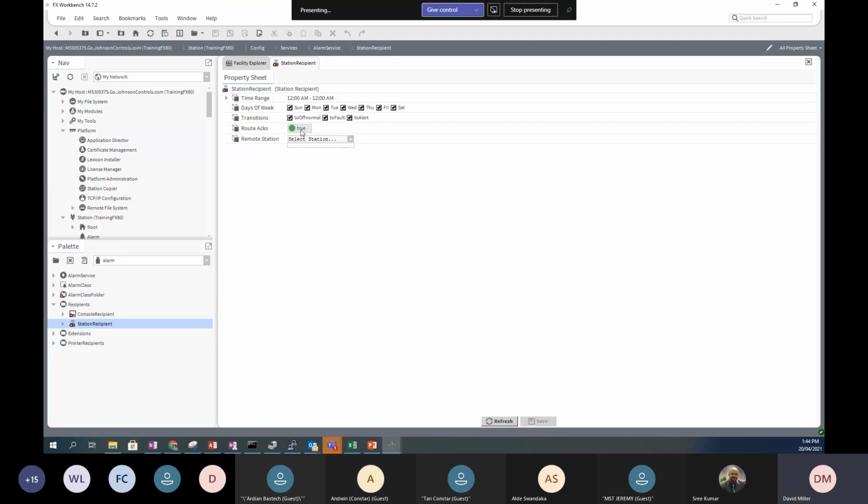It sounds like when it's just one alarm, it all seems to work, which means you probably got it all set up correctly, and then FX80 has been routed correctly. If we test single points, alarm triggerings, deletes, if we synchronize and clear out itself, no issues. When there's more than 5 or 10 alarm multiple entries to the FX server itself, sometimes there's a leftover and it keeps the alarms popping up again.